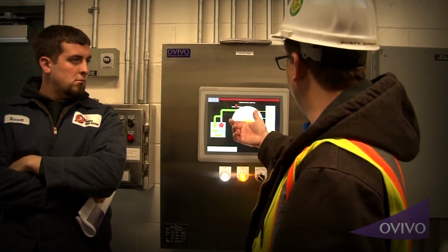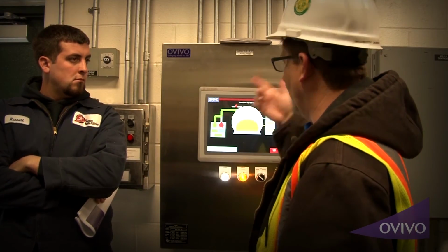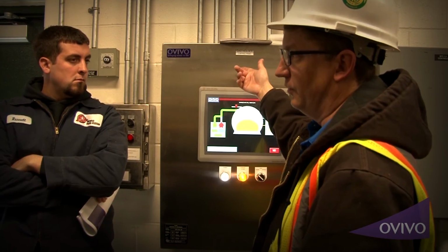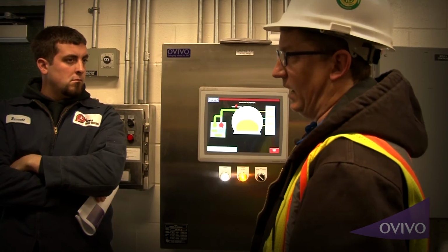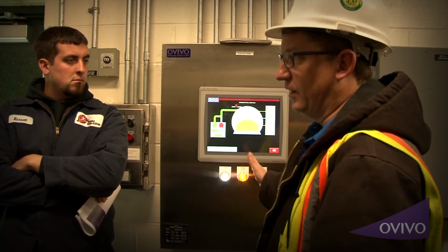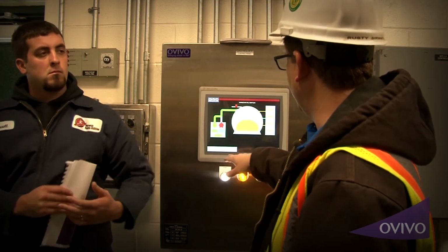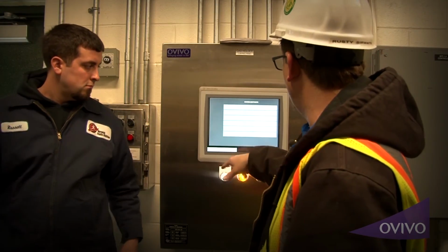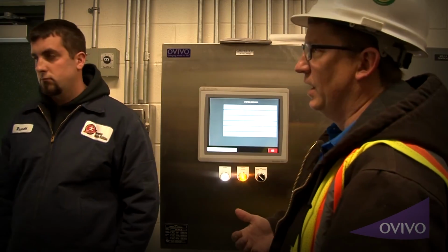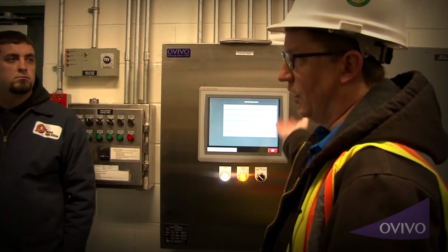But you did also notice that it went straight to UPS mode, or UPC mode, which is the battery pack on it. So the battery pack does work, and the second I turned it back on, it was standard back in there, and all of the set points are still the same. So even if you lose power, all your set points are going to be there.